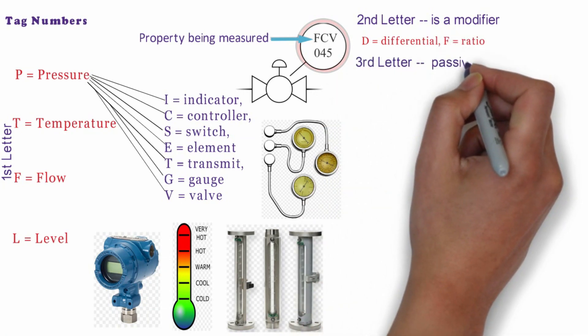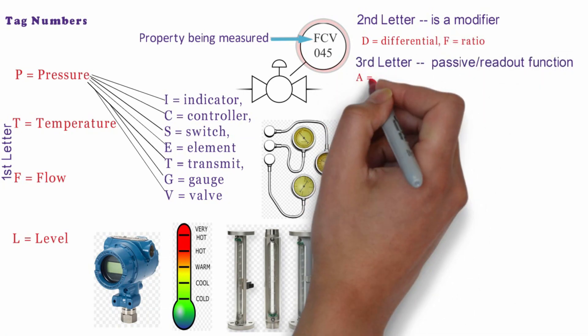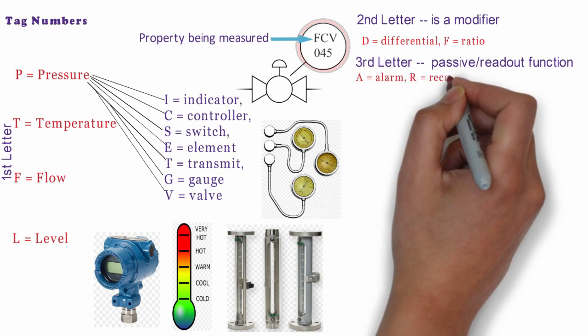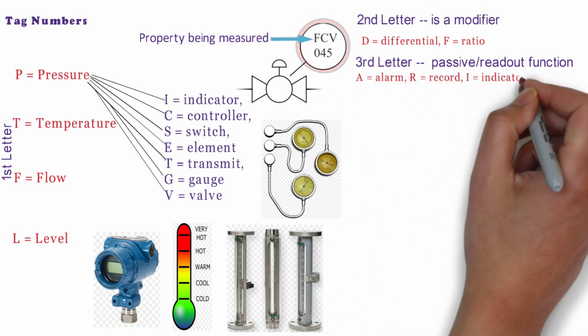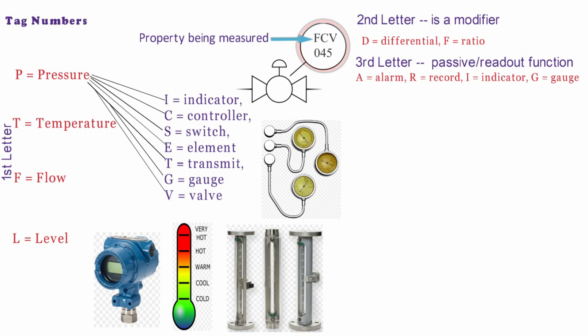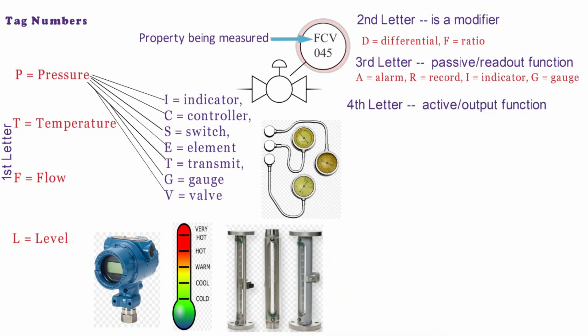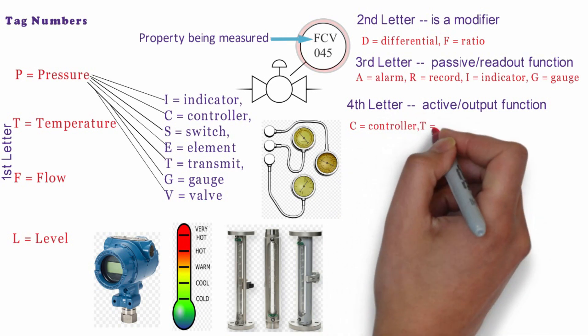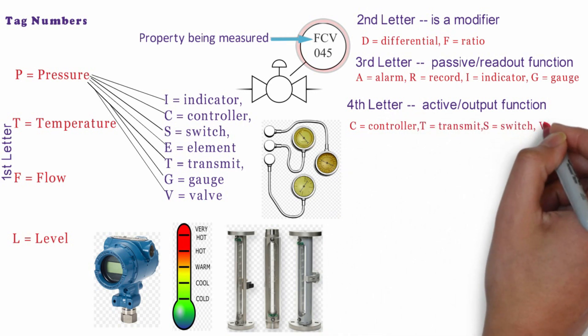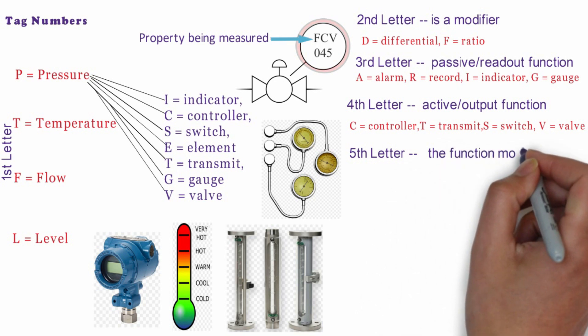Third letter indicates the passive or readout function like A is for alarm, R is for record, I is for indicator and G is for gauge. Fourth letter is for active or output function. Like C is for controller, T is for transmit, S is for switch, V is for valve.